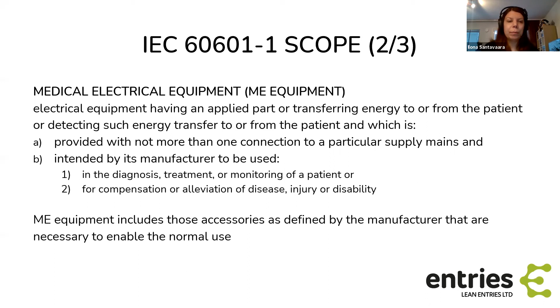And then there's also a definition of medical electrical systems. So this, on the other hand, is a combination of items of equipment, at least one of which is medical electrical equipment. So this is a wider concept. If you have multiple different equipment in your setup, you might even have some that are not medical. You might have a laptop computer or things like that, but these form an ME system. And why is it important? It's because some clauses in the standard apply to medical electrical equipment, so those must fulfill some requirements, but then there are also requirements for the whole medical electrical system, for example interconnectivity. But it applies to both unless it is stated that this is only for ME systems, for example, like in the title of one of those chapters.